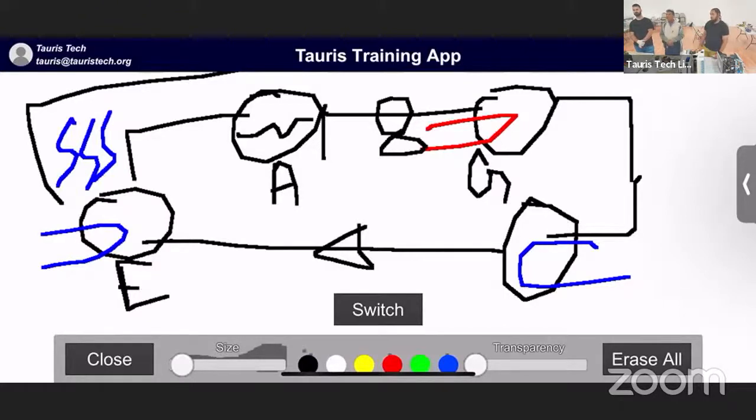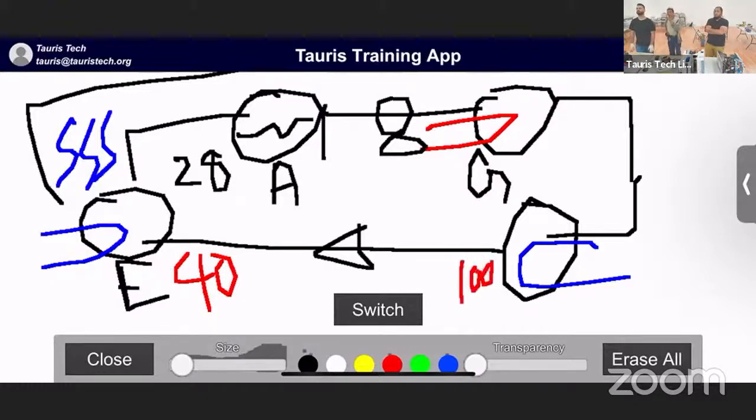So we have a deep vacuum. Inside of the evaporator side, it's gonna be like 28 inches of mercury. It's gonna be a deep, deep vacuum. And I'm boiling the refrigerant at, let's call it 40 degrees, 35, 40, whatever. So I'm boiling the refrigerant at 40, it gets sucked out into the absorber, it mixes with the solution, I pump it into the generator, I heat that up, and then it goes into the condenser. So I need to condense it inside the condenser, right? So in my condenser, I'm gonna be condensing at like 100 degrees, but my pressure is still gonna be like 25 inches. So both sides of the machine, the high side and the low side, is a very, very deep vacuum.